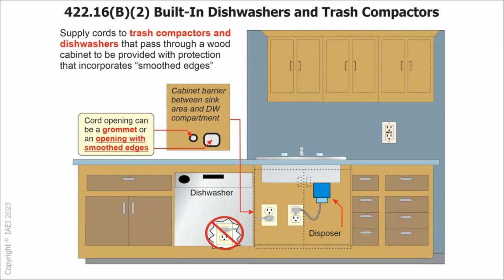So, supply cords to trash compactors and dishwashers that pass through a wood cabinet are to be provided with protection that incorporates smooth edges. So, this is a code change because the wording in the 2020 said that it had to have a fitting, and there was no fitting listed to go through wood. So they've put smooth edges in there, something to help you go through, not a listed device to run a cord through. They've just cleaned up the wording because it was a little ambiguous in the last code cycle.